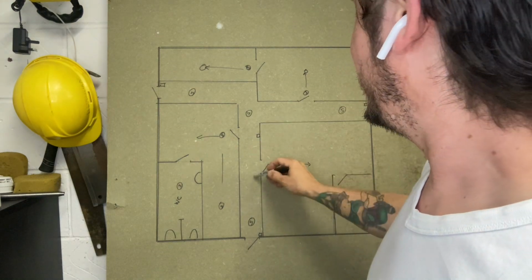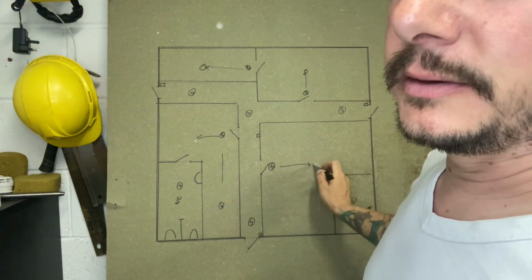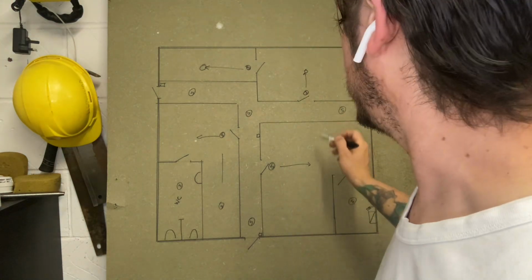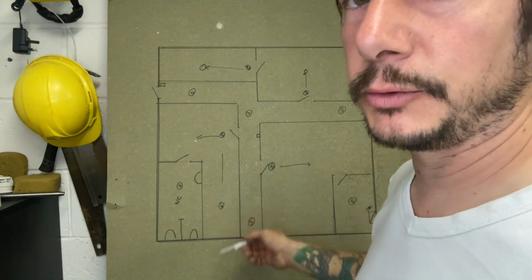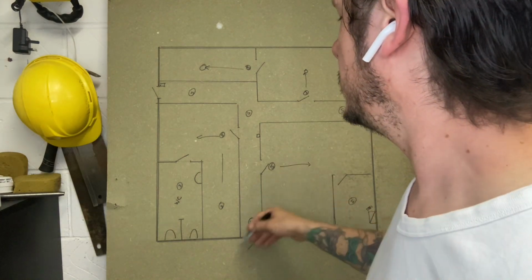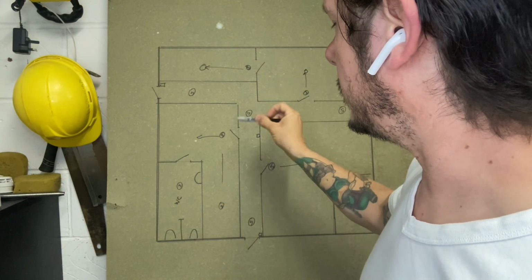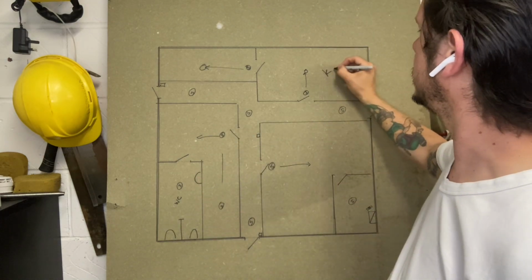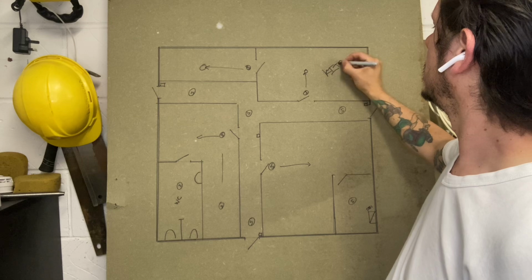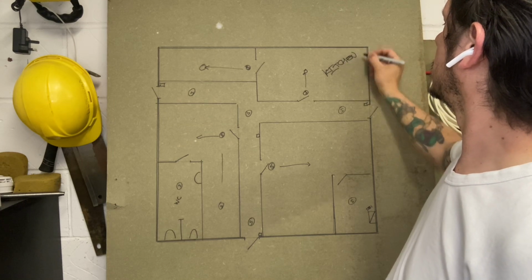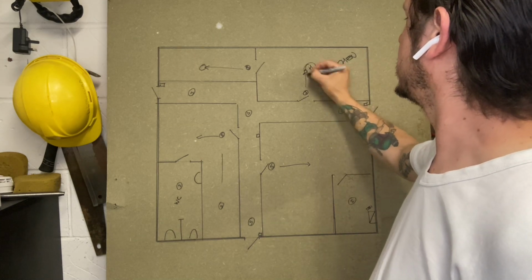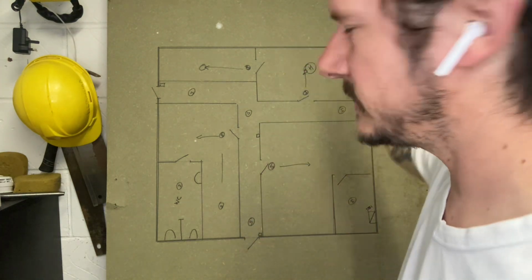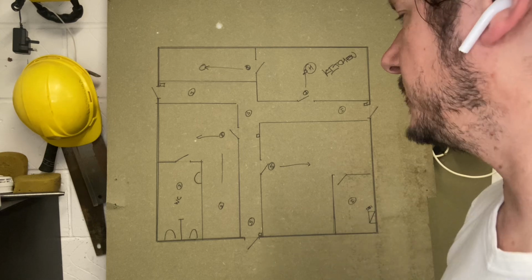LD3, these guys would actually wind up being in the middle of the room. I don't think I would be as inclined to monitor the door with them. It's not really the point in a house. So you're more just adding on rooms. So then you get to LD2. You're going to throw the kitchen into it, and so this is the kitchen. So we're going to bung a heat detector in there for our LD2. But then again, you get into LD1, total coverage, kind of similar to L1.